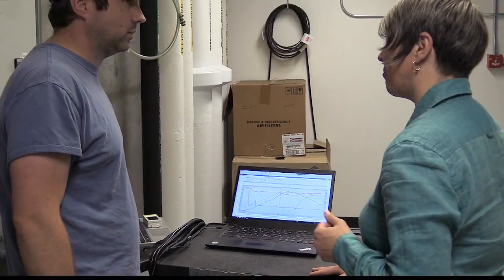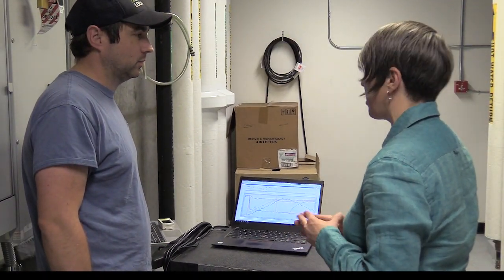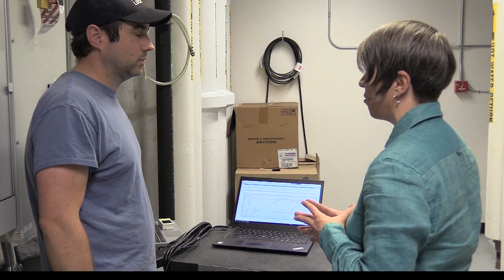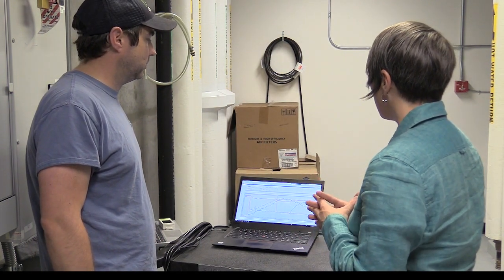Great, thanks Pat. So it looks like the economizer is working as we would expect it to, at least in cooling mode. So now we'll go ahead and download the data from the logger and the sensors that we placed and see how that compares.